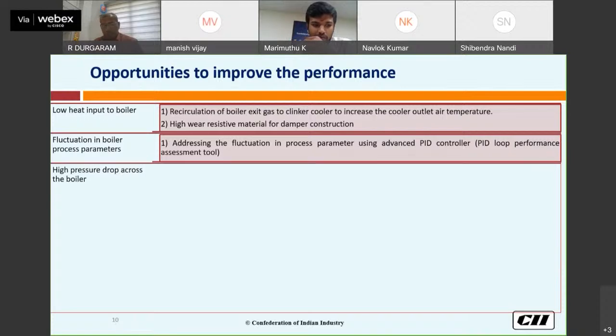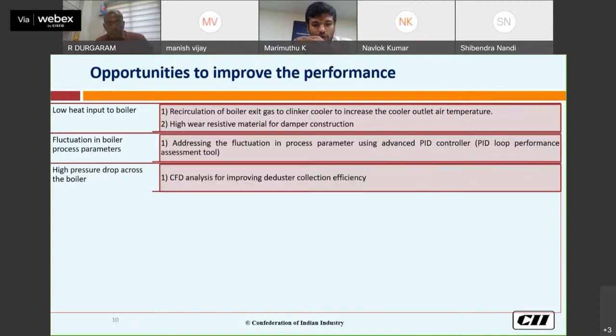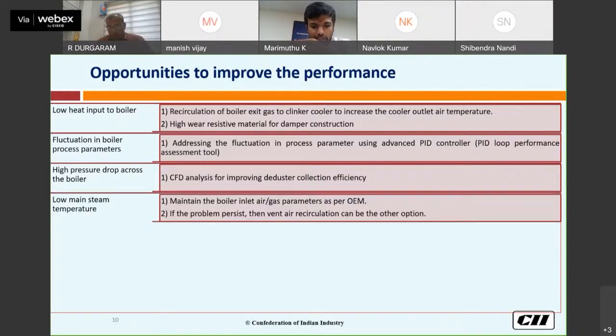Then another one, high pressure drop across the boiler. The study conducted in 6 units says there is no defect like this. If we have any high pressure drop, we can go for a CFD analysis for improving the dust collection efficiency and also for the WHRS boiler. Then low main steam temperature. As I said, if the design consideration and the actual heat input are a mismatch, then this can happen. So maintain the boiler and the inlet air gas parameters as per OEM. Or if the problem is present, then we can go for vent air recirculation to increase the main steam temperature.